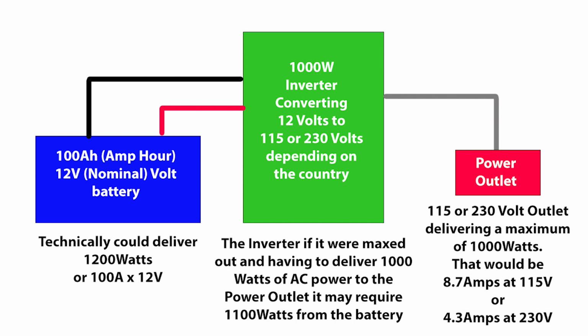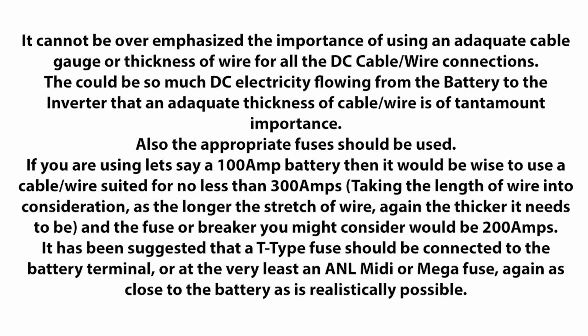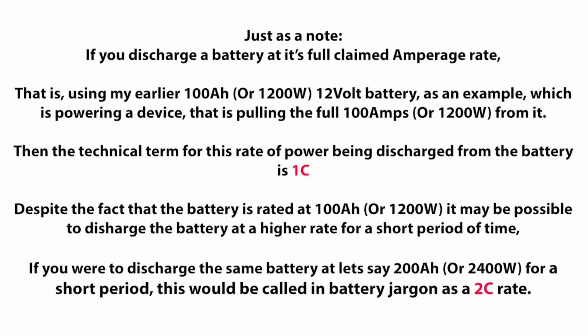if being discharged, that is, at 1100 watt rate. Don't forget the battery to inverter cable wires must also be adequate enough in gauge and thickness to handle this much DC electricity flow. Please see my number 5 electrical wiring tutorial. Incidentally, discharging a battery at its full stated rate would be referenced as a 1C discharge rate. 1C could discharge the battery of all its stored power, if it was full to start off with, in 1 hour.